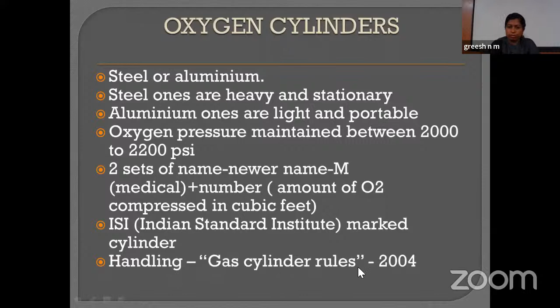Coming to the oxygen cylinder, this is very well explained by Dr. Parthasarathi sir. I'm just going to say it in bits. Oxygen cylinders can be either steel or aluminium. Steel ones are heavy and usually stationary, whereas aluminium ones are light and portable. Oxygen pressure maintained in the cylinders is between 2000 to 2200 psi. There are two sets of names for the cylinders. The older one is A, B, C, D, but the newer name has an M. M means medical, and there is a number associated with the oxygen cylinders. This number indicates the amount of oxygen compressed, in cubic feet. The cylinders have to be marked with ISI, that is Indian Standards Institute, and the handling of gas cylinders is according to the Gas Cylinder Rules 2004.